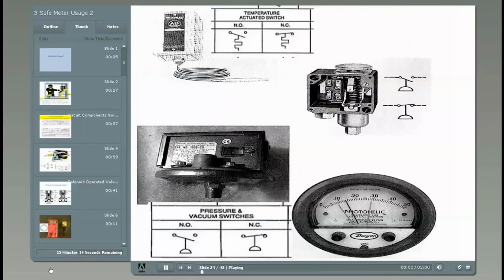Tell us about temperatures and pressures. The device at the top left is an electromechanical temperature sensor made by Allen Bradley. It uses mercury-filled capillary tubing to sense temperature via vapor pressure technology. The normally open NO contact will close at the selected temperature, and the normally closed NC contact will open at the selected temperature. If this temperature switch was set to 300 degrees, the NO would close at temperature rise of 300 and above, and the NC would open at temperature rise of 300 and above.